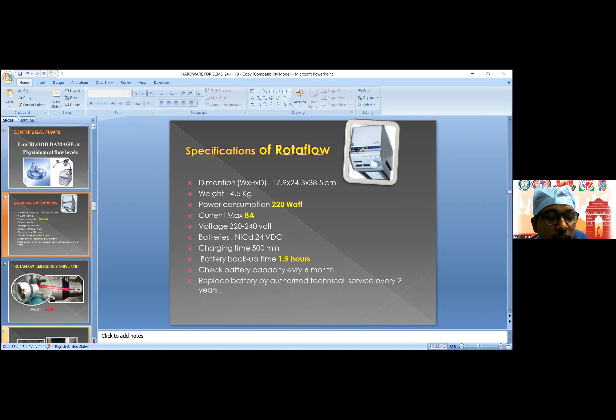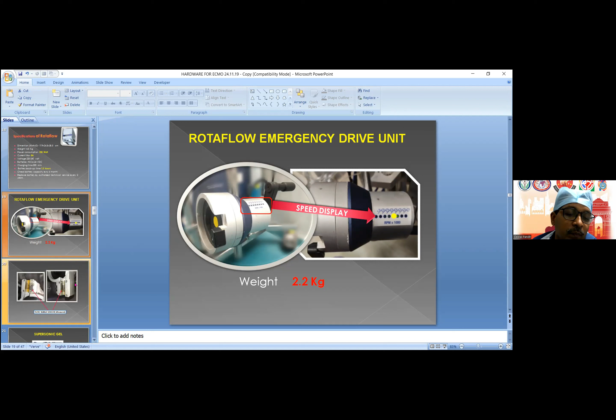Most centers now have more than one console in their institute. But previously most institutes had only one machine. If the patient is dependent on this machine for either a respiratory or cardiac issue, interruption of the machine may become a life and death situation. So the industry has generated another backup console. This is the emergency drive unit. Some companies provide two consoles for one set of machine, and this console we can operate by hand. Put the pump here, and through hand we can generate 1.5, 2, 2.5 or 3 with a multiplier of thousand, meaning 1,500, 2,000 or 3,000 RPM, whatever was set in the console.